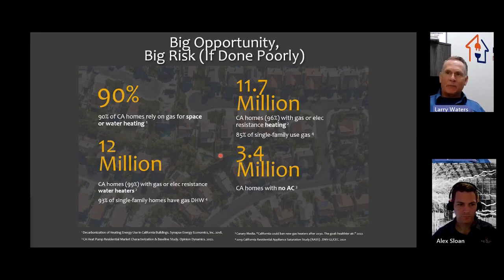Okay. All right. So heat pumps in California, big opportunity or big risk if we screw it up. So 90% of California homes rely on gas for space and water heating. There's 12 million houses out there that have gas or electric resistance and water heaters, but there's 3.4 million houses out there with no air conditioning in them. So if we're going to electrify and change out gas heating systems in houses without air conditioning, and we have a heat wave like the East Coast has had, or Texas has had, or we had in the central part of the United States this year, if we have that and we have a lot more air conditioning units online than we did before, and a lot of them aren't installed well or they're too large, this extra 3.5 million houses coming on with air conditioning is going to be devastating.